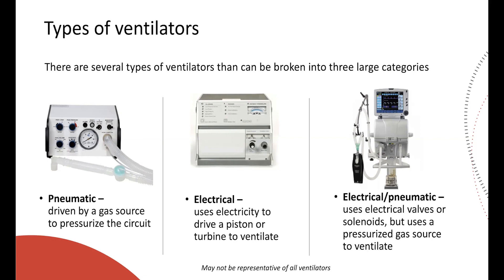The second type is electrical, meaning it uses electricity to drive a piston, turbine, or blower to ventilate. For example, the LP-10 has a piston that pushes forward to give inspiration, with exhalation done through a valve. The type you'll most likely see in intensive care combines electrical and pneumatic — the best of both worlds. It uses electricity to control valves and solenoids, while also using a pressurized gas source to ventilate, allowing for faster response time and fancy monitoring with flow sensors.